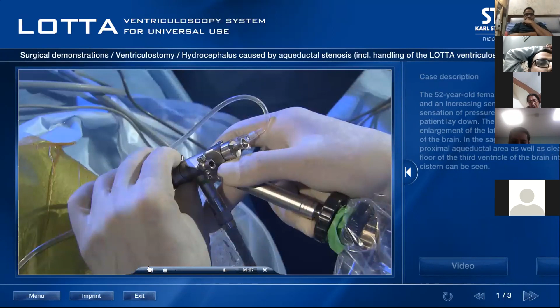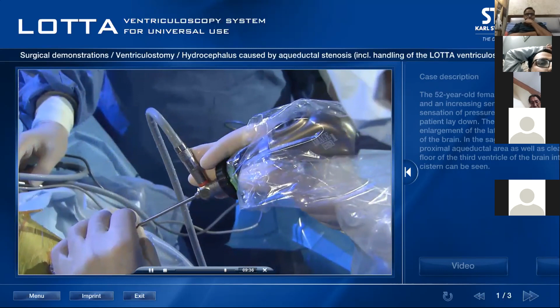After performing the ventriculostomy, the ventriculoscope is removed and the 30-degree endoscope is inserted for inspection of the prepontine cistern. Now you see this red color on the adapter. It means the surgeon is using a 30-degree scope. Always your camera head button should be facing the top. The light cable has moved to the 12 o'clock position. That means the surgeon is now going to see the view at 6 o'clock.